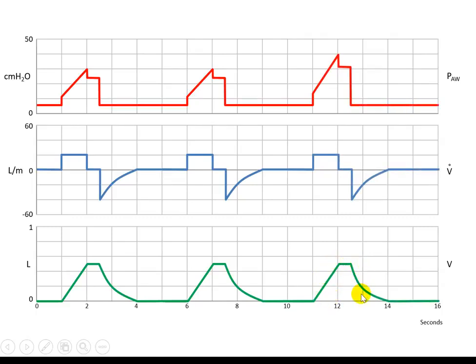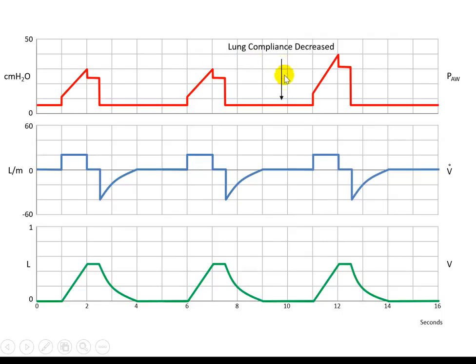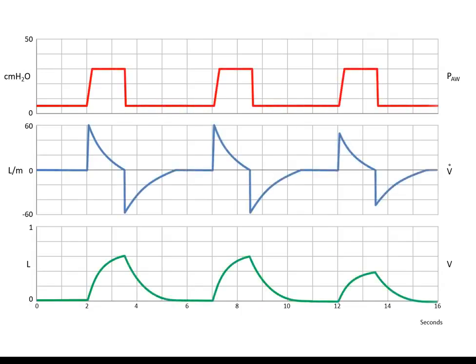In volume control mode, the machine will try to deliver the set tidal volume, and the pressure will increase to overcome the airway resistance and the lung and chest wall elastance. If the lung compliance decreases, the pressure required to deliver the same tidal volume will increase in order to maintain the tidal volume as it is set.